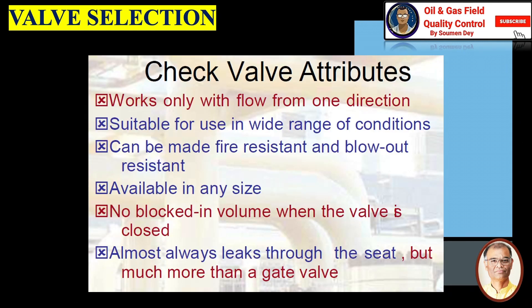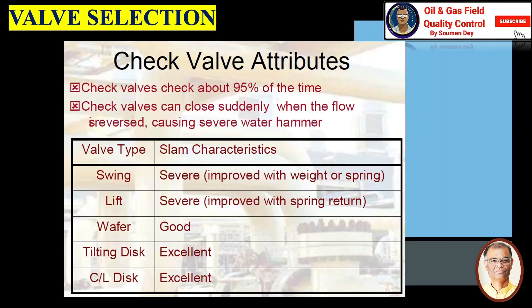Check valve: as the name suggests, it checks the flow in one direction. It works only with flow from one direction, suitable for use in a wide range of conditions, can be made fire resistant and blowout resistant, available in any size. There is no blocked-in volume when the valve is closed, but it almost always leaks through the seat — much more than a gate valve. Check valve checks about 95% of the time. Check valve can close suddenly when flow reverses, causing severe water hammer.